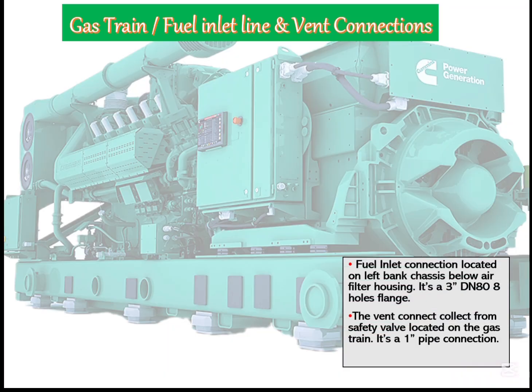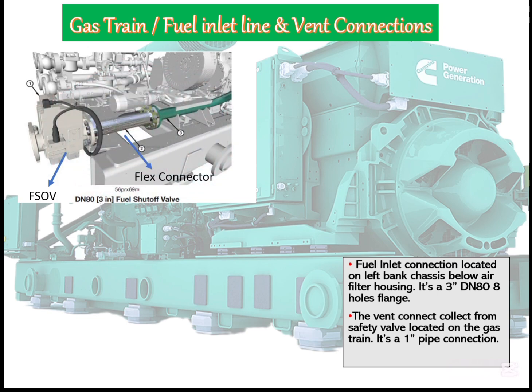Gas train or fuel inlet. The fuel inlet connection is also located at the front side of the engine, below the air filter housing. It is a 3-inch pipe with an 8-hole flange at the end. It's not 4-hole, it's an 8-hole flange line. In the same way we already mentioned, for all connections we first use a flex connector. This is a flex connector and the FSOV, the fuel shut-off valve. From here we select our fuel connections to the gas connections. The customer will complete the lines.